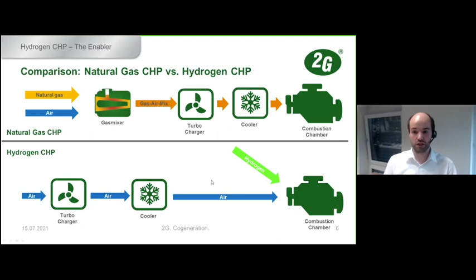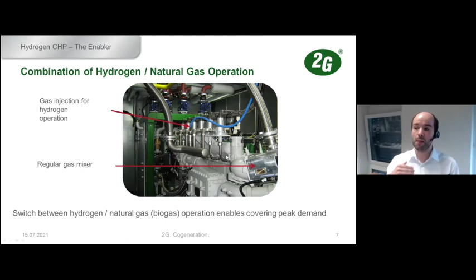A nice side effect is that you can apply both technologies together, injecting both hydrogen and natural gas. So even if you retrofit an existing natural gas cogen to hydrogen, in case hydrogen isn't available in sufficient amount or at sufficient price, you can still continue to operate on natural gas or biogas. This enables coverage of peak demand based on fuel availability.